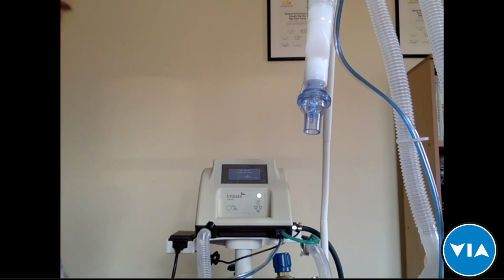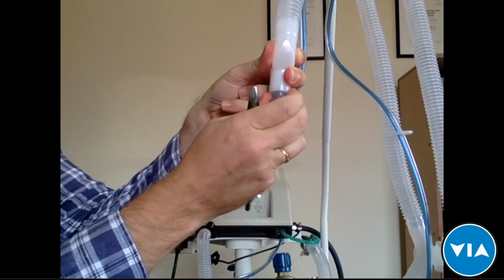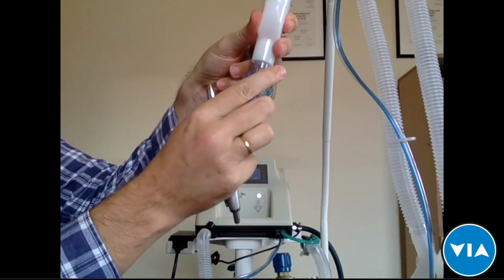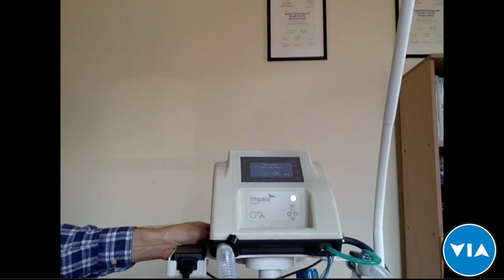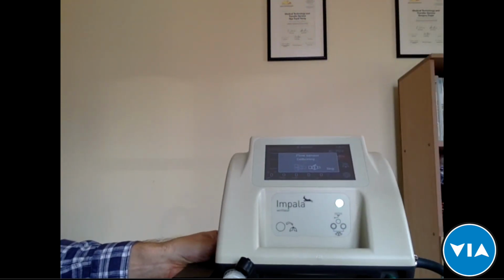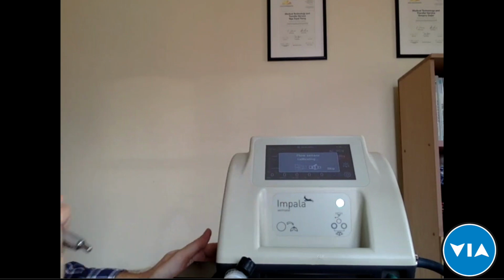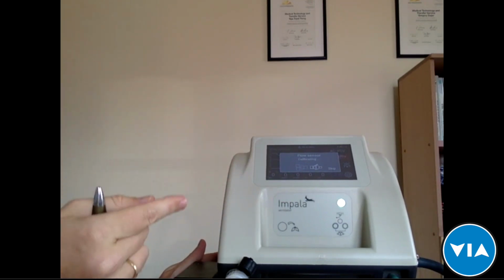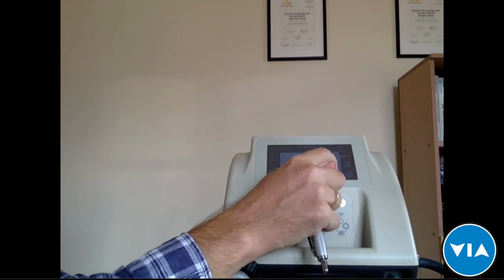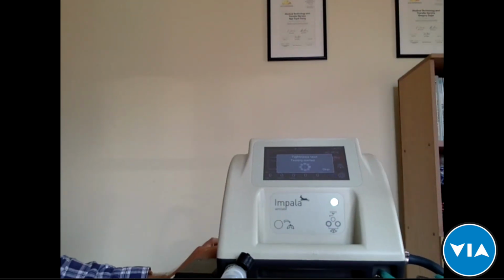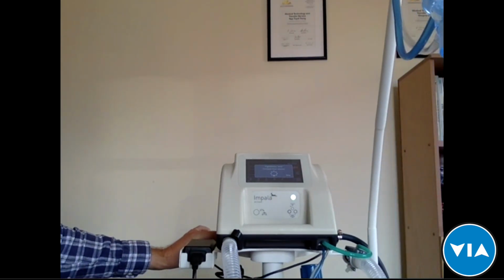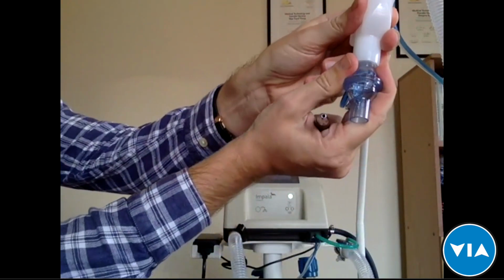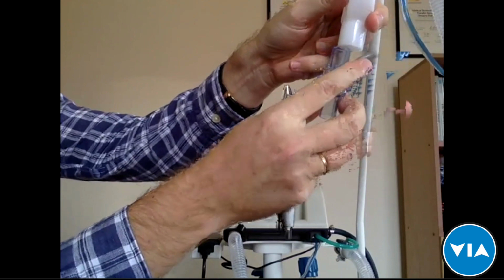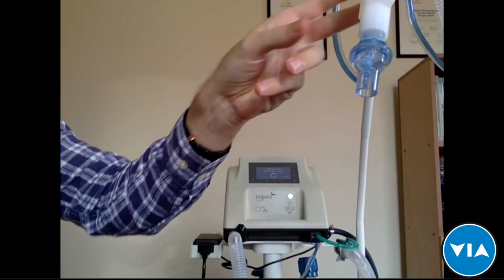And for that calibration, it's very important to flip that sensor for the second step in that calibration, which is described by the software as well, as you can see on the screen. Now we have to flip the sensor, and calibration continues. I skip that because we don't need to watch that again. And the final step is I have to move the sensor back to the original position.